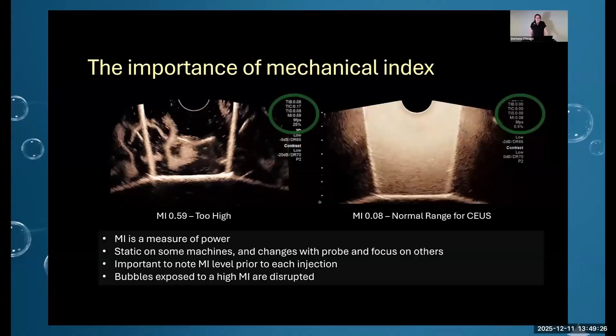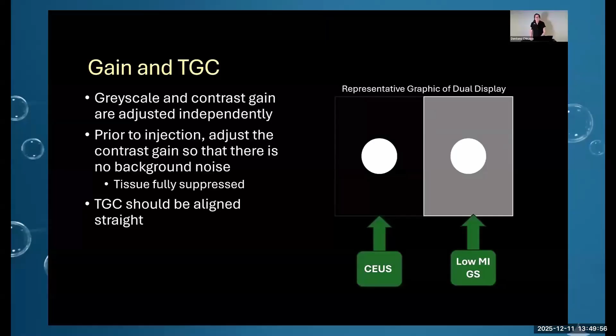Gain is important. So grayscale and contrast gain are adjusted independently. So prior to injection, we'll just show you have your grayscale side, your low MI, and then prior to injection, you want to adjust the contrast gain so that there's no background noise. So you turn your contrast gain up, and then you pull it back till the image is fully suppressed or the tissue is fully suppressed. Your TGCs should be aligned and straight.